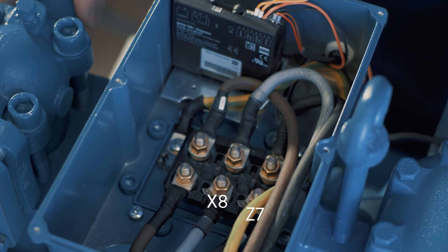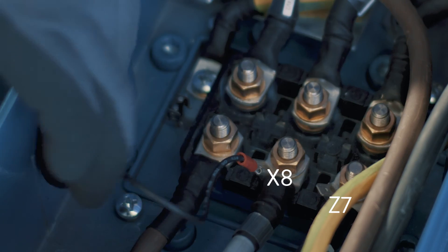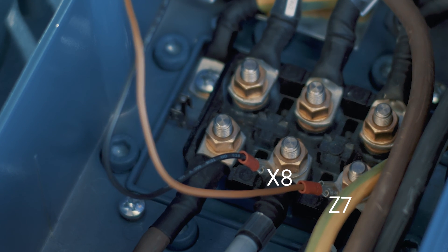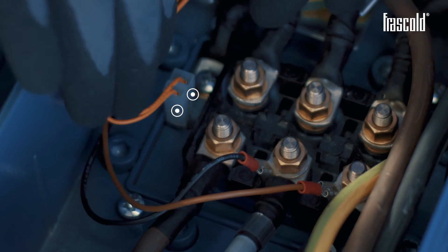Connect the Kriwan protection device to the two eyelets previously positioned. Insert the brown connector into the corresponding pin Z7 and the black one into pin X8. To conclude the connection, wire the Kriwan protection device to the two thermistor probes. Close the junction box by tightening all the screws of the cover with a Phillips screwdriver or a screwdriver.